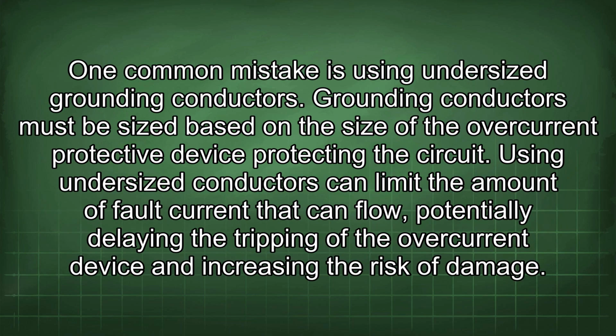One common mistake is using undersized grounding conductors. Grounding conductors must be sized based on the size of the overcurrent protective device protecting the circuit. Using undersized conductors can limit the amount of fault current that can flow, potentially delaying the tripping of the overcurrent device and increasing the risk of damage.